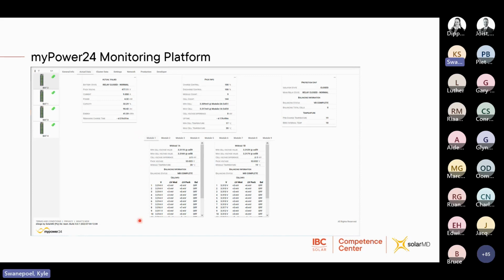If we move down to the individual modules, you'll see here that there's module 1A and then 1B. The naming convention actually comes from the previous generation of high voltage batteries, where each battery module had 2 BMSs because there was 32 cells, but now there's only 16 cells in each module, but the convention has remained the same. So module 1A will be the CAN bus, one line connecting from the BMU to the first battery module will become 1A. Whichever line connection from 1A to the second module will become 1B, and so forth. So you'll have 2A, 2B, 3A, 3B, and so forth.